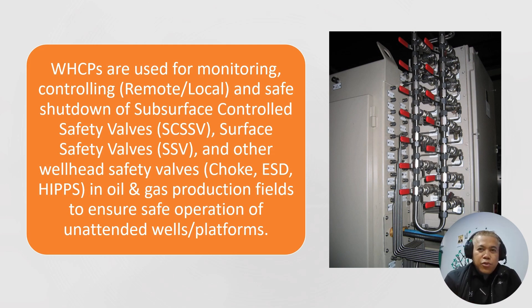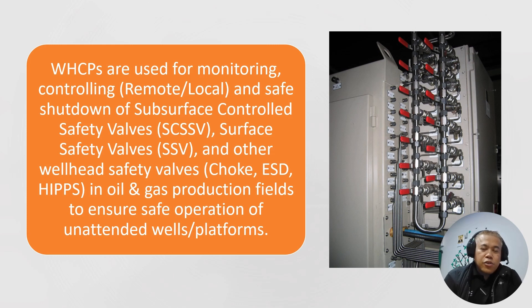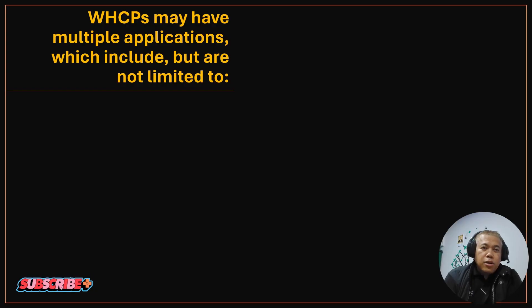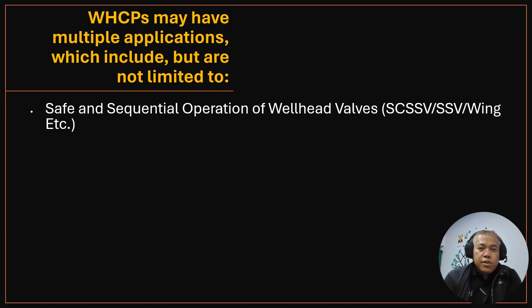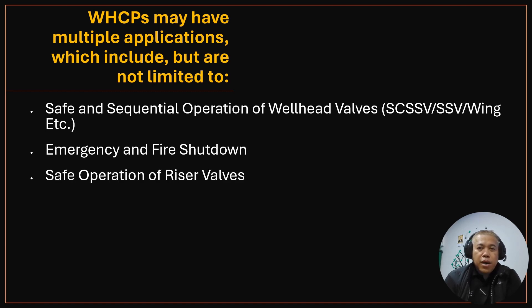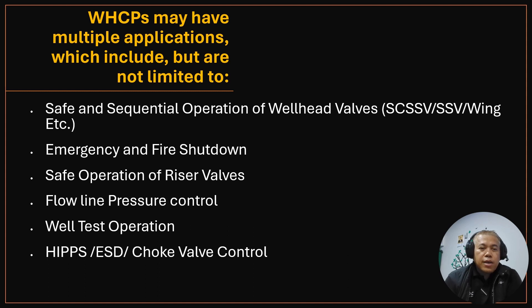The wellhead control panel is connected to our safety valves, wing valves — surface safety valves — and we also have choke valves and HIPPS. This is the oil and gas production field. To ensure safe operation of unattended well platforms, because our wellhead is an unmanned platform, we need remote control. Wellhead control panel applications include safe and sequential operation of wellhead valves and wing valves, and emergency and fire shutdown.